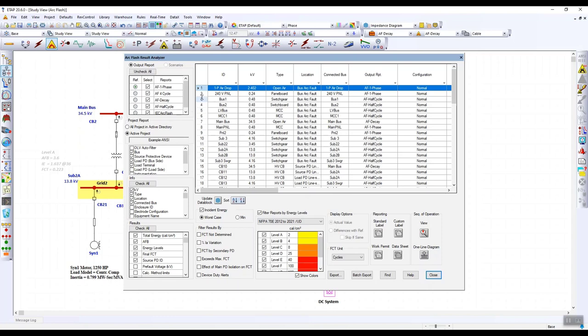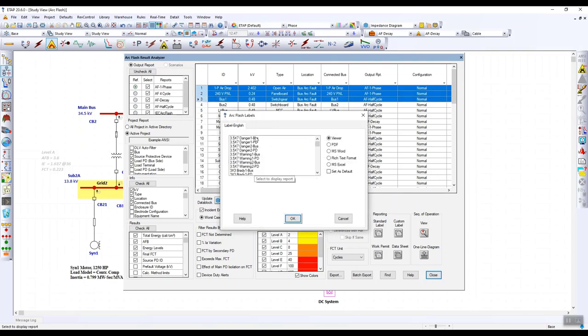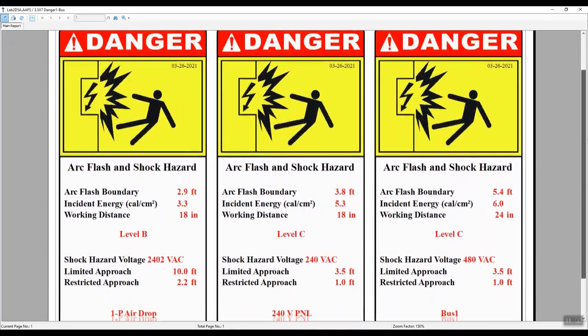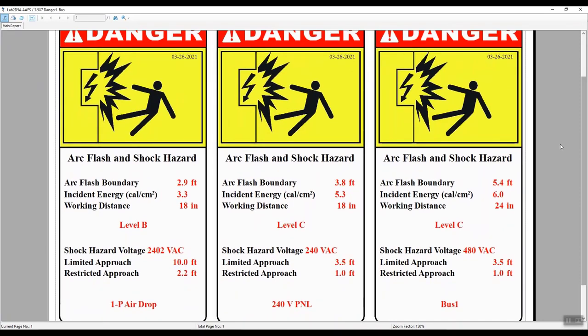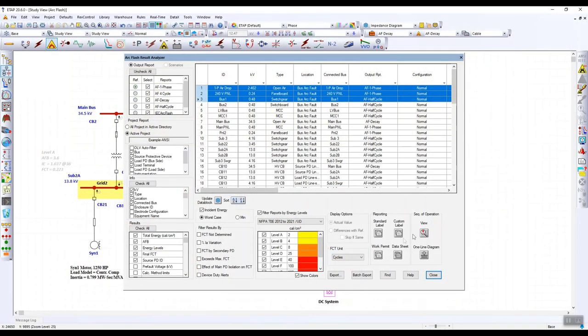We can then generate a label for the worst case incident energy for a single device or multiple devices. Here we have a huge template list that you can select from with labels from Brady, Avery, Durlabel, and more. On this label, we see the arc flash boundary, incident energy, working distance, energy level, shock hazard, and appropriate working distances. You can also generate custom labels, work permits, and data sheets for your devices.